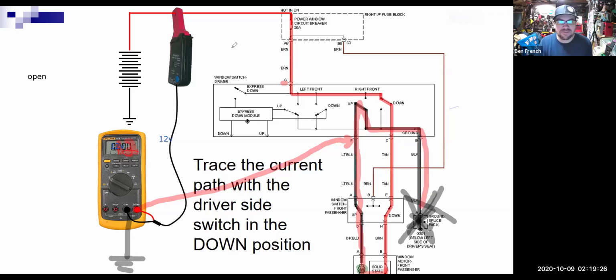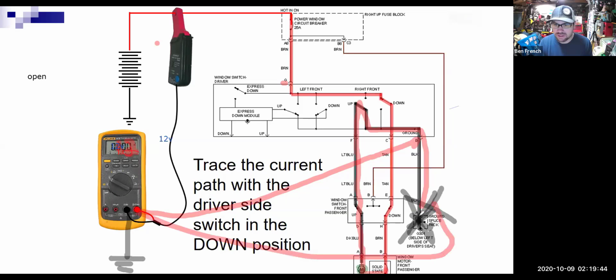And that would tell me, oh, I must have an open on my ground circuit, right? I could start testing it at different spots - I can move my meter lead over to terminal B. If I don't see anything there at terminal B, then I'm going to go straight here and see what's going on. So if you're not measuring any current flow at all, you know, hey, I have an open circuit. That screams I've got an open.